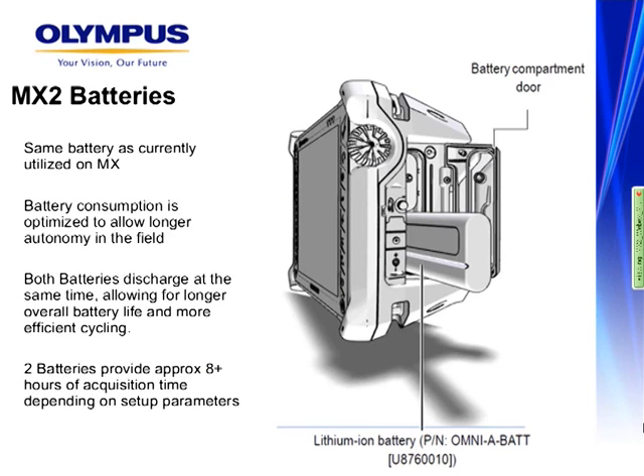The MX2's improved battery performance includes the same battery as the MX, but it is optimized with more efficient cycling by discharging both batteries at the same time for improved performance between charges and overall battery life. Two fully charged batteries provide approximately 8 hours of use depending on setup parameters. The MX2 can operate with one or two batteries, and either one can be removed and replaced while the instrument is in operation.